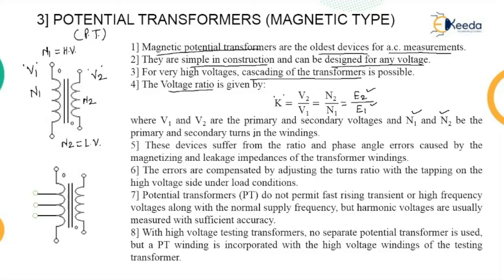These devices suffer from ratio and phase angle errors caused by the magnetizing and leakage impedances. The magnetizing current — used to magnetize the transformer — causes errors. To compensate, the turns ratio is adjusted. For this adjustment, tappings are generally provided on the high voltage (primary) side of the transformer.